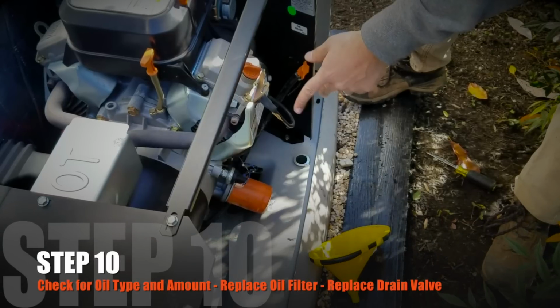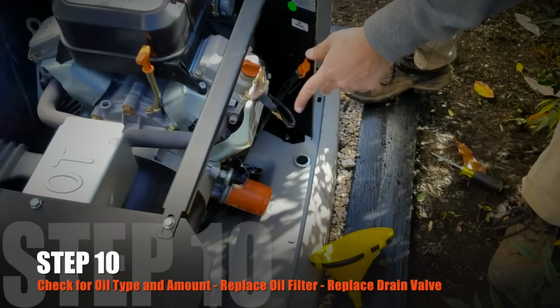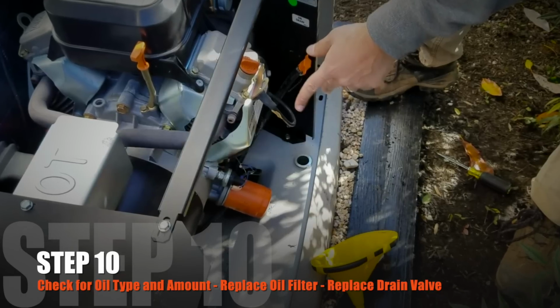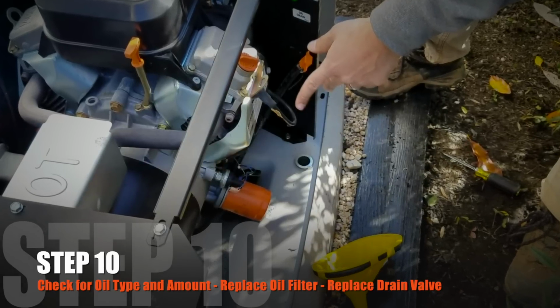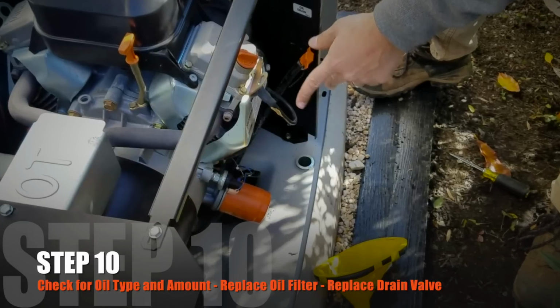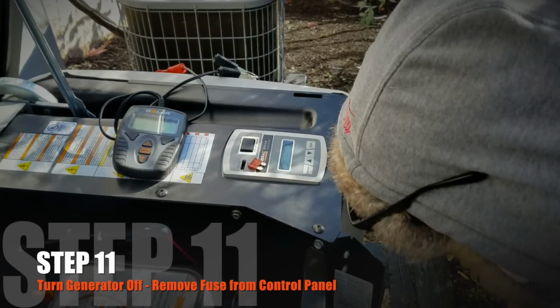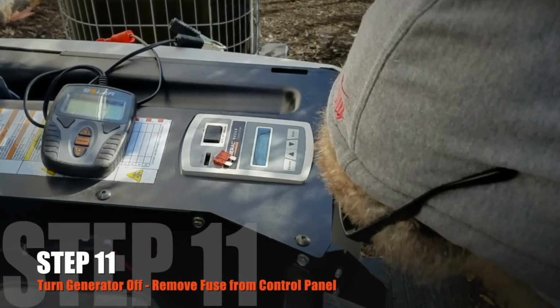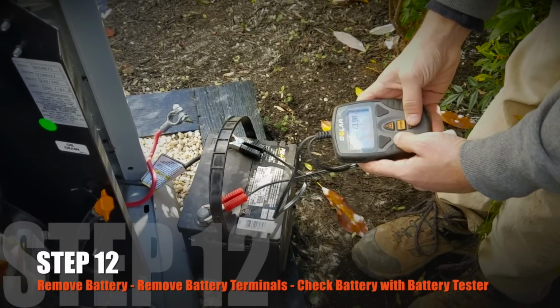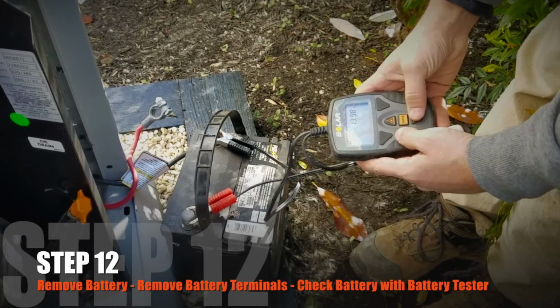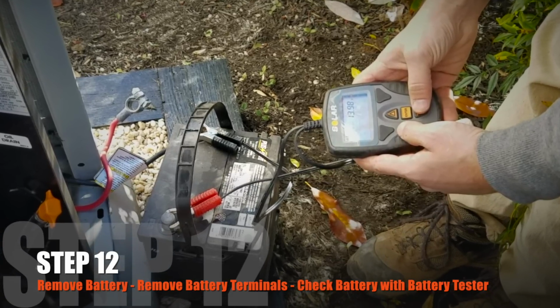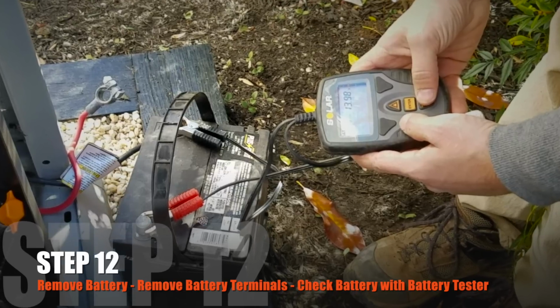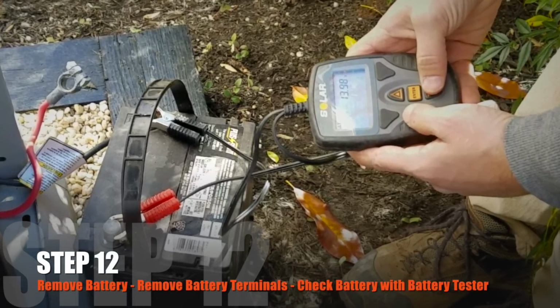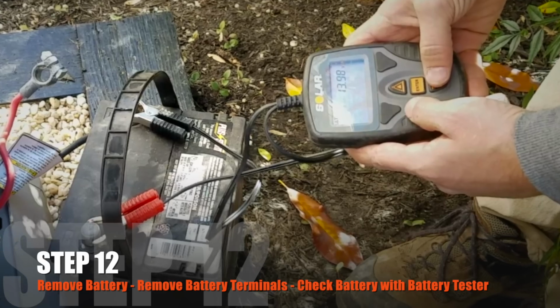Step 10. Check your Generac generator model number and owner's manual for the amount of replacement oil your unit requires. Insert a clean oil filter, then secure the oil drain valve and air filter case wing nuts. Step 11. Before checking the battery, turn your unit off and remove the fuse from the control panel. Step 12. Remove the battery and both terminals. It is important to remove the black or negative terminal first, then the red positive terminal. Using a battery tester, check the charge. If the battery is good, reinstall into the unit.